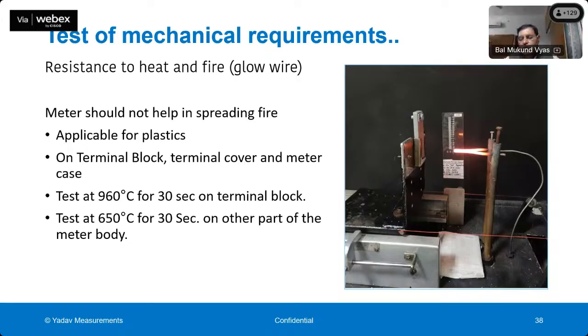And the terminal block should not burn, and it should not melt and fall down. So you can see there is a white tissue paper placed below this glowing element, and if the terminal block is melting and the drops are falling on this tissue paper, then it is not considered a suitable plastic. So this is the test, and a similar test, except that the temperature is 650 degrees centigrade, is applied on the meter case and terminal cover also. So this actually controls the quality of plastic. A normal plastic cannot be used on electricity meters. It has to be a good quality engineering class plastic which passes this test.